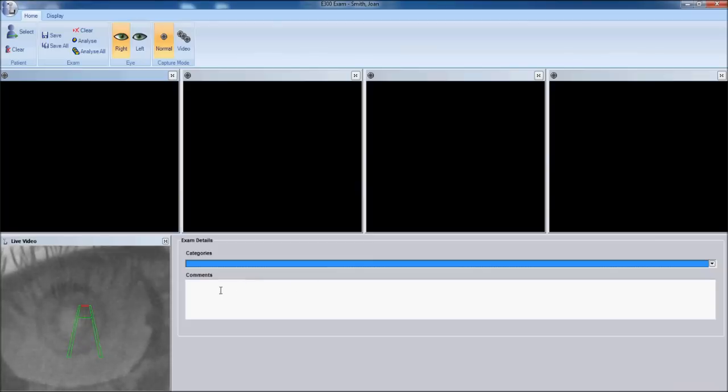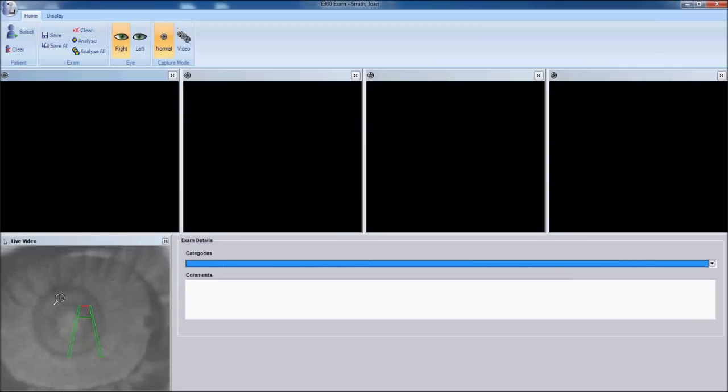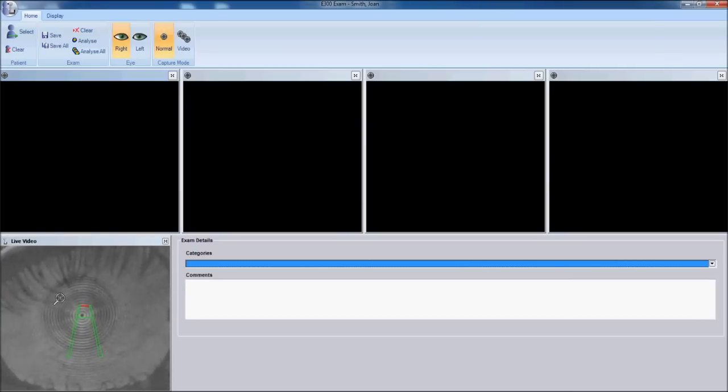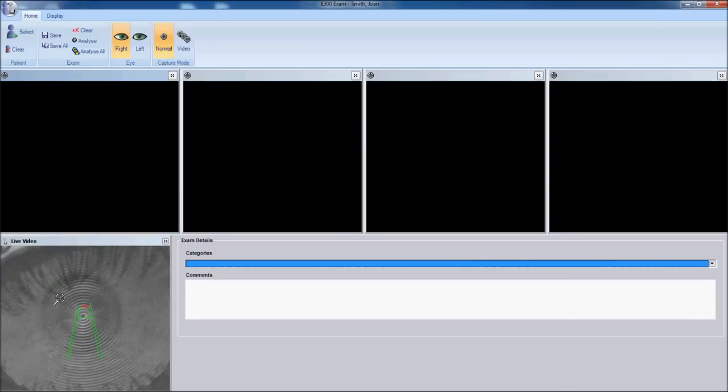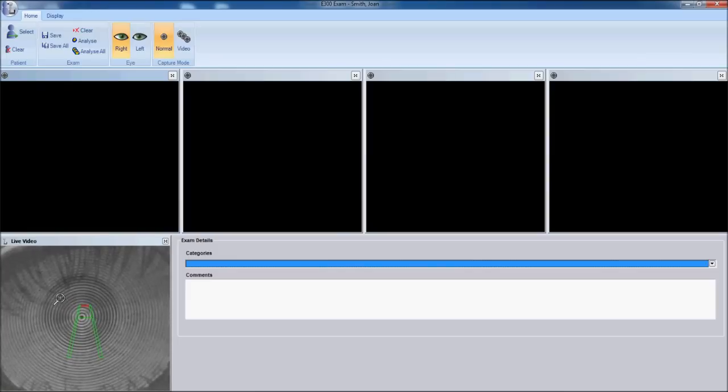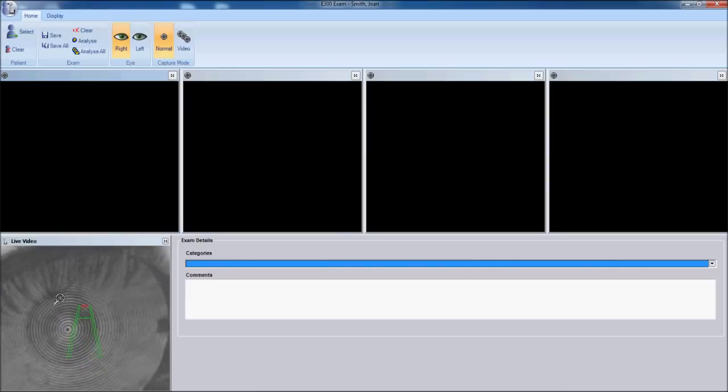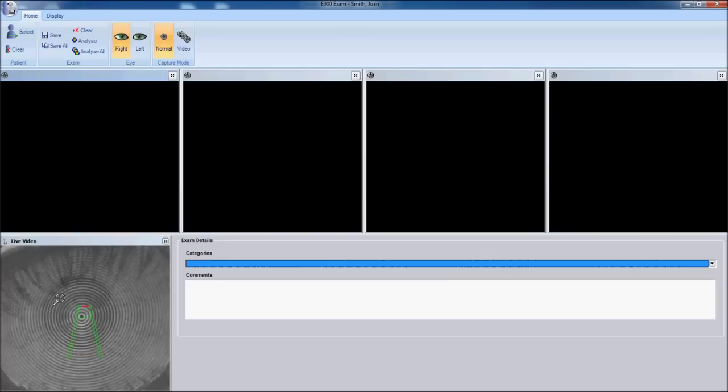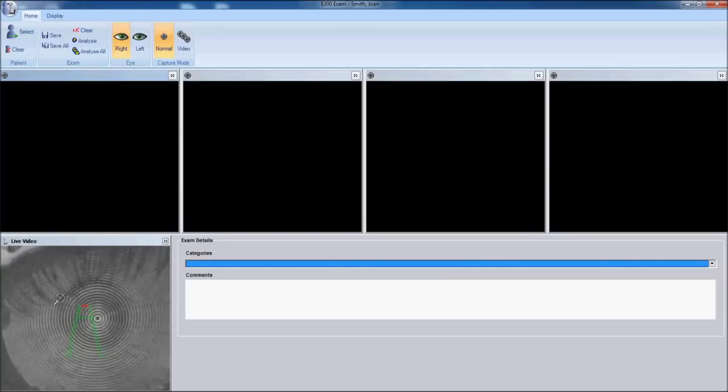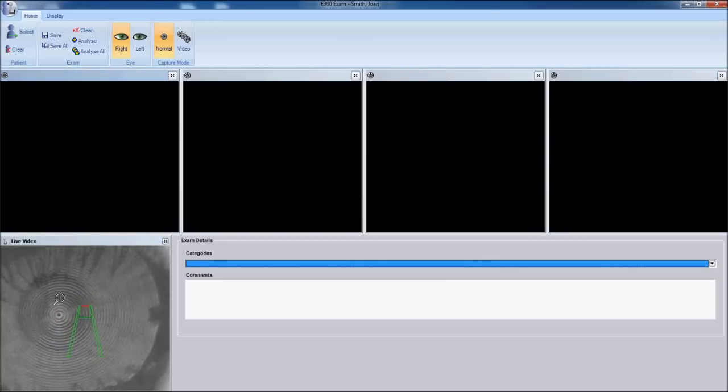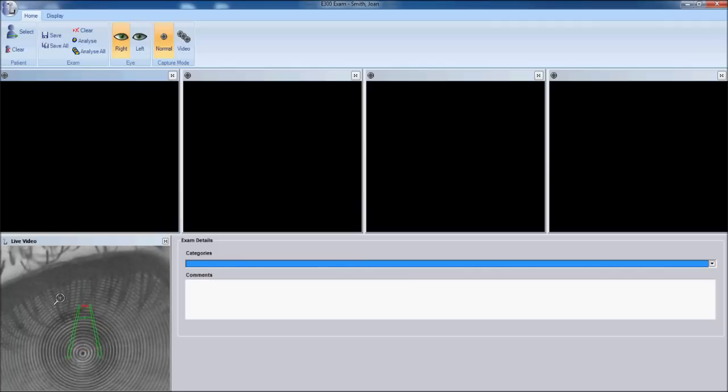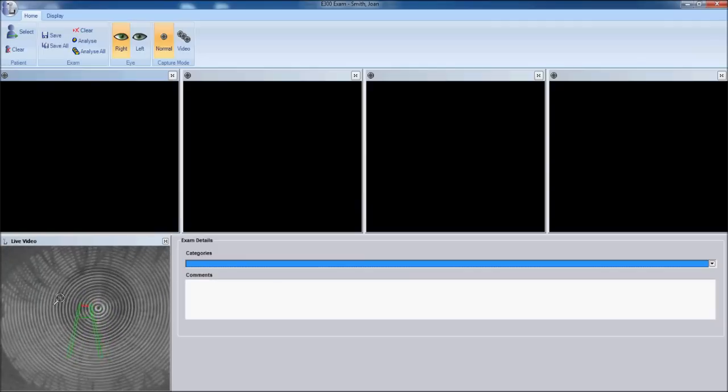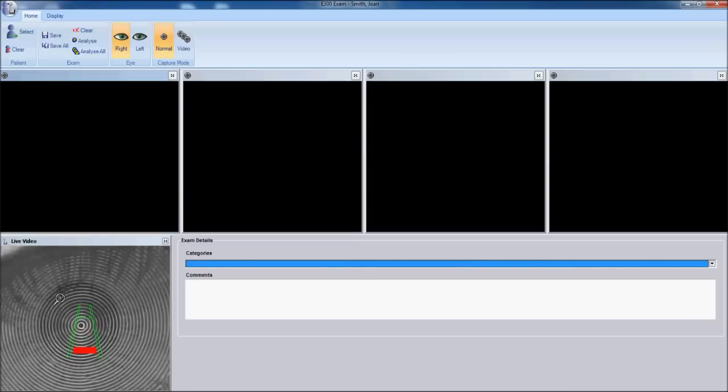With the capture window up you're focusing on the lower left video image. With the green crosshair control the centration of the instrument's focusing point on the apex ring of the placido reflection. You can move your joystick nasal or temporal. You can rotate the joystick to lift the instrument up or down. But center that green crosshair on the apex ring.